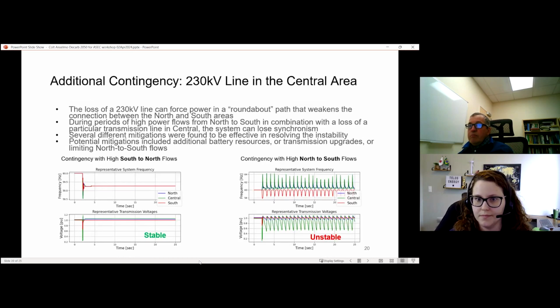So next slide, please. Here we have the additional contingency, which was the loss of a 230 kV line in the central area that we analyzed for this scenario and not for the others. And what I want to point out here on the left is that for most hours of the year, we didn't have an issue with this contingency. The system kept stable. However, when we have this particular flow on the rail belt, things can get weird. We have a problem. This happened specifically when we have the flow on both interties going from north to south. So the flow on the entire rail belt is going from north to south.